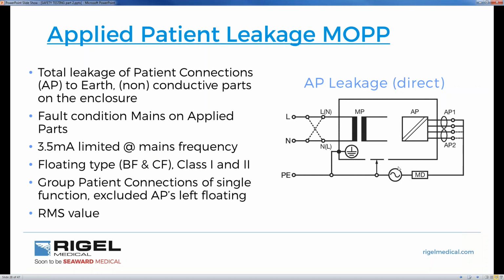So this is our isolated voltage, which is linked between our protective earth and our chassis. The measuring device is measuring any of the mains on applied part, and hopefully this should prove any isolation between our applied parts back to protective earth. So this is what we're proving. We're proving isolation if mains voltage were to fall on to our applied parts back to earth, because we don't want that. Similar thing with 60601 and 62353.